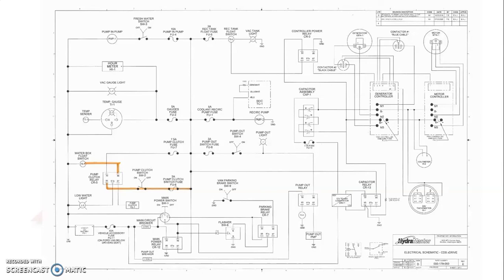Circuit number 6 is the pump clutch switch. So we run the power for the relay through the switch to the float switch. The only power that's going through the switch, and we've tried to do this on most of these, is power that only operates the relay. It doesn't operate the component directly. That's to prevent wear and tear on the switches themselves.